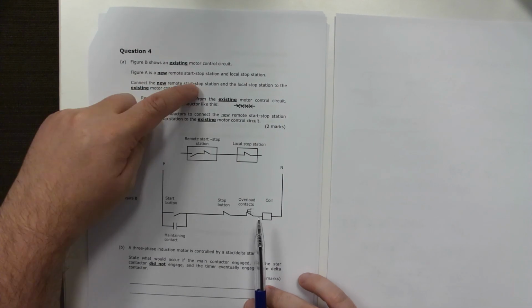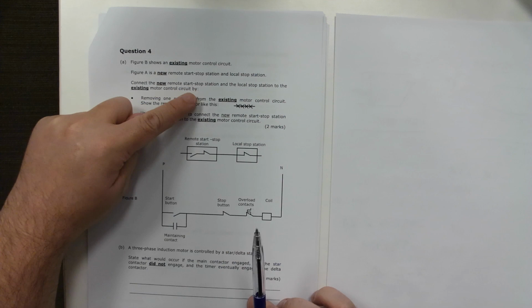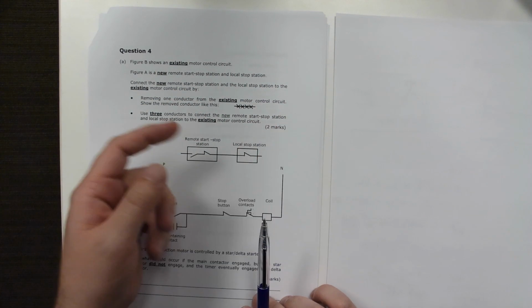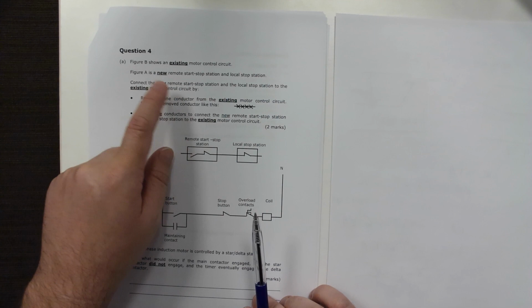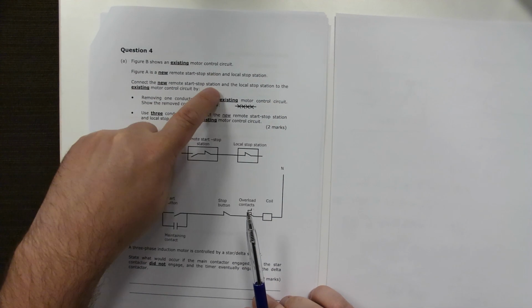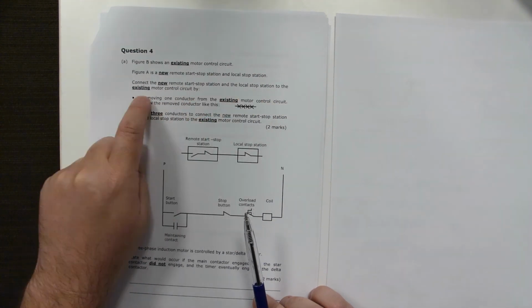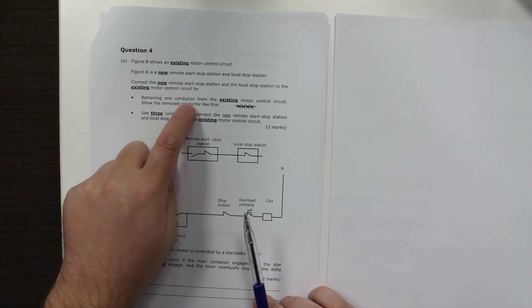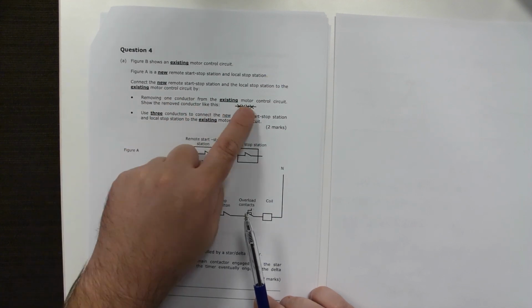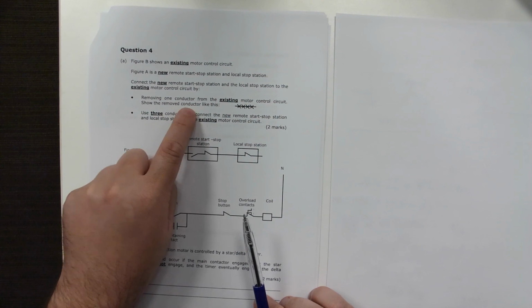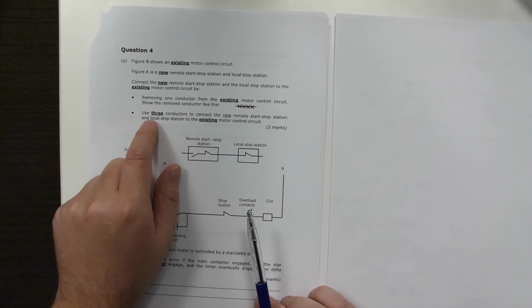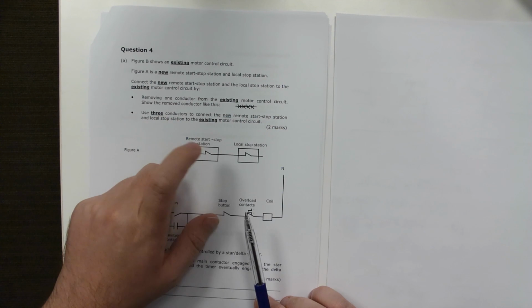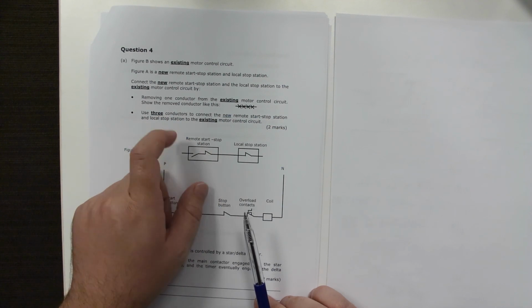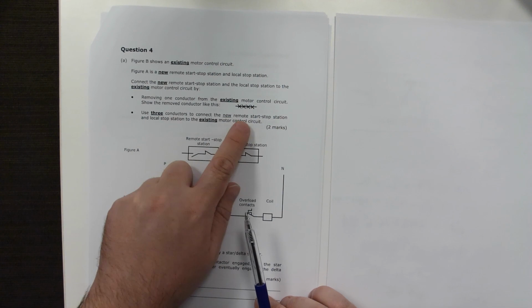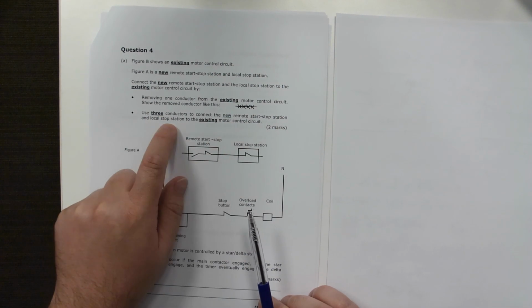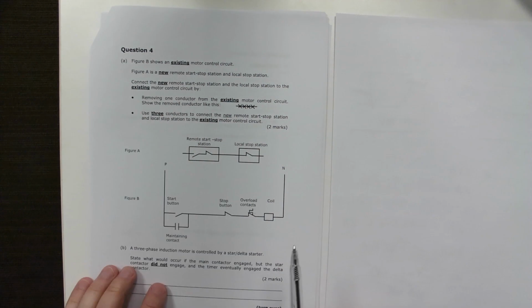Figure A is a new remote start stop. So that's figure A, remote start stop, and local stop station. Connect the new remote start stop station and the local stop station to the existing motor control circuit by removing one or more conductor from the existing motor control circuit. Show the removed conductor like this. So we're just going to put X's through it. Use 3 conductors. So it's going to be 3 conductor remote start stop station to connect the new remote start stop station and the local stop station to the existing motor control circuit.